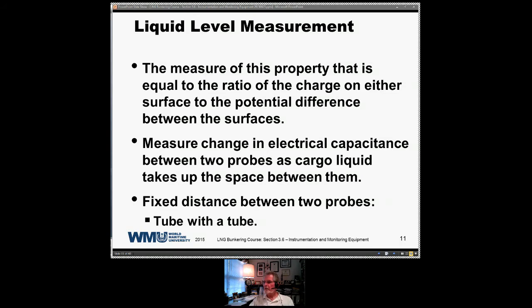Okay, and there's a fixed distance between the two probes throughout the entire depth of the tank. So in our case, on the old ships that I was on, we were looking at about a 35 meter tank. The length of that tube was 35 meters, a double tube, tube within a tube. The distance between those two probes was fixed, regardless of where you were in the length of that tube. And when you get this difference in potential across it, you then could measure the actual liquid level of the tank.